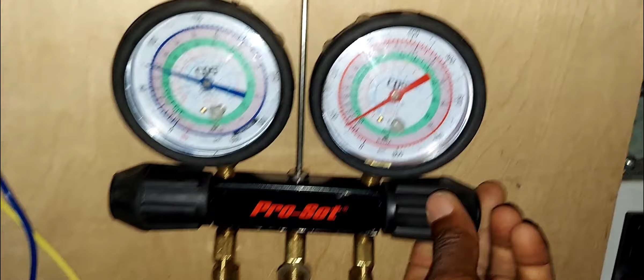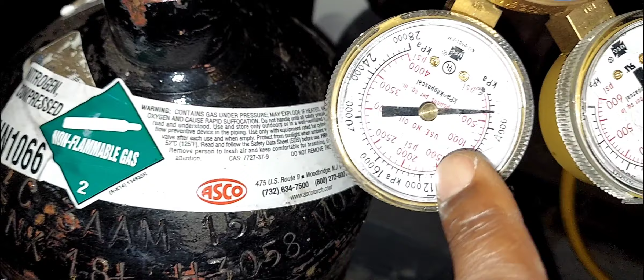Now, we're going to build up the high side so we can trip this switch. We're going to increase this pressure. Turn this in. Build the pressure. I want to go to 410. Now remember, my compressor is still on. You can see me, I'm doing cooling, baby. All right, so I'm going to trip this high pressure switch, increasing my pressures on my regulator, turning that in. And this needle, that's the tank needle. Which one is the tank needle? I think this is the tank needle. Is it? Let's see. Okay, this is working properly. I'm not even quite sure. Nonetheless, it's not what this video is about.